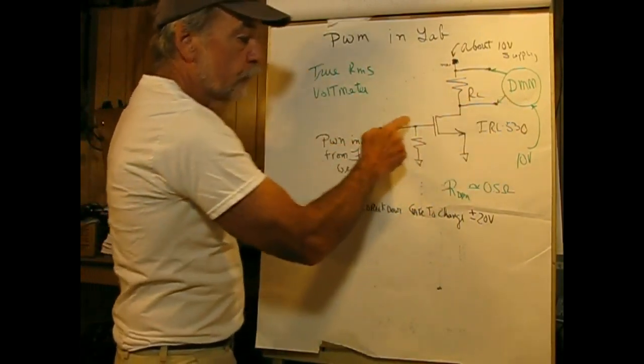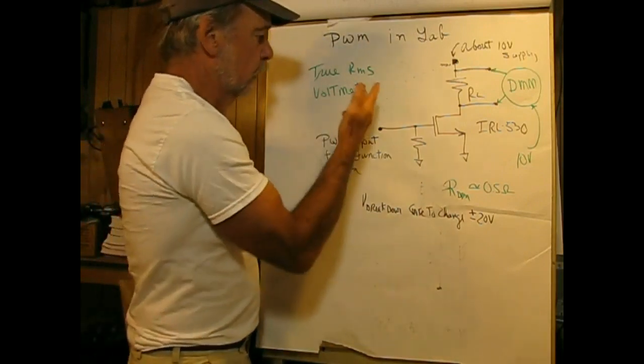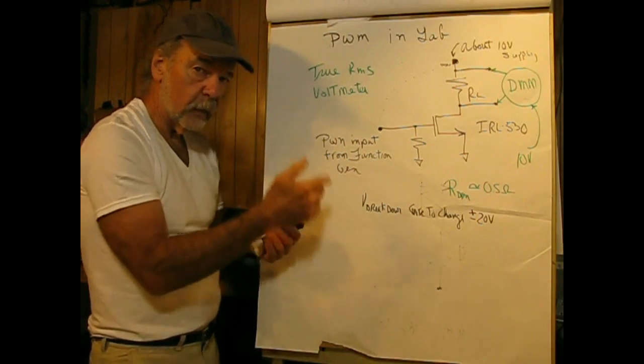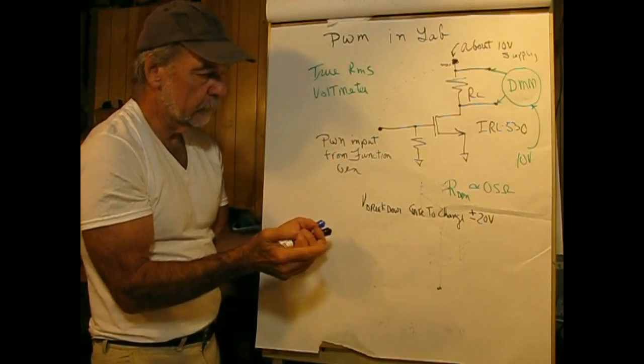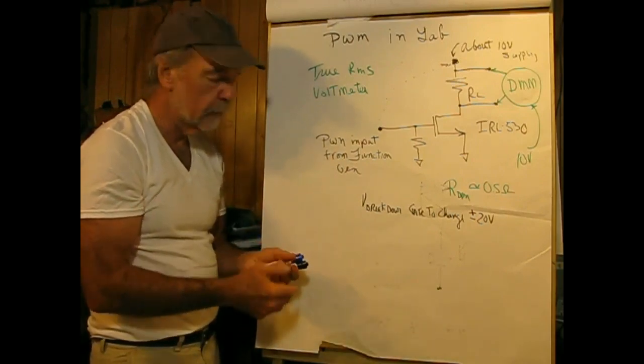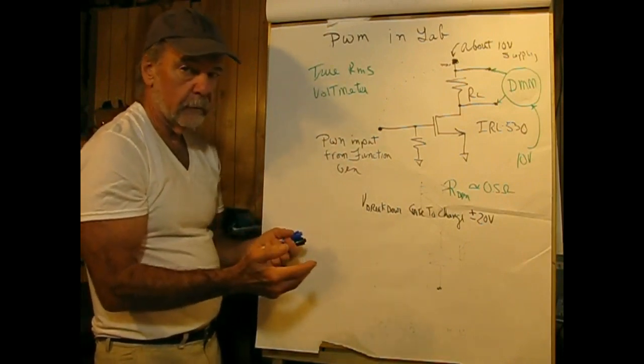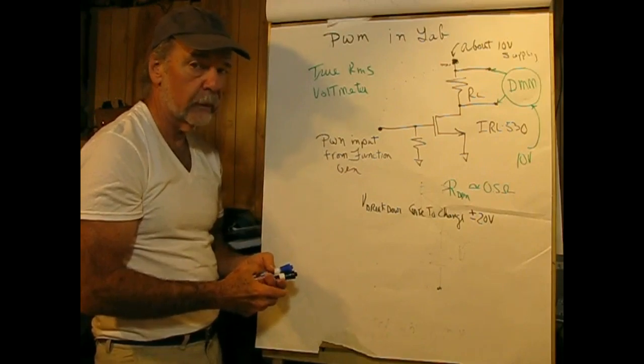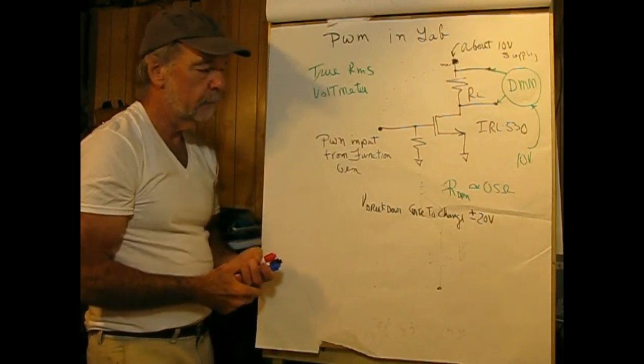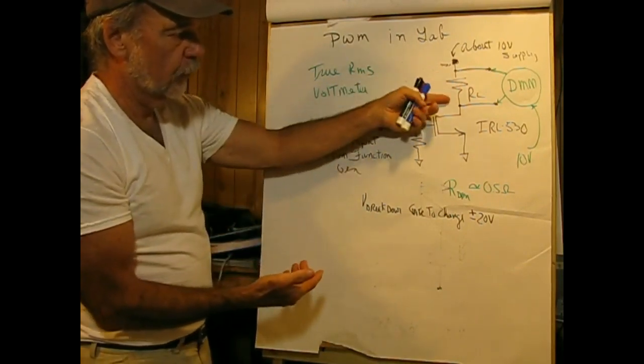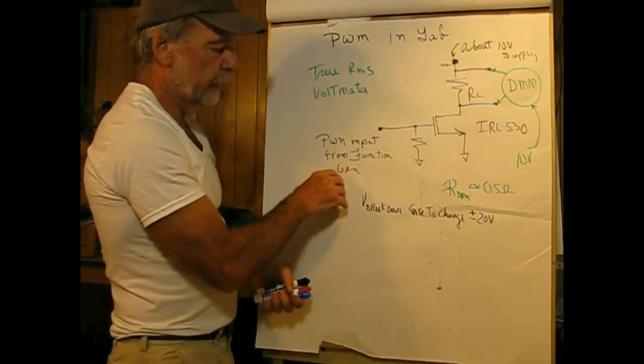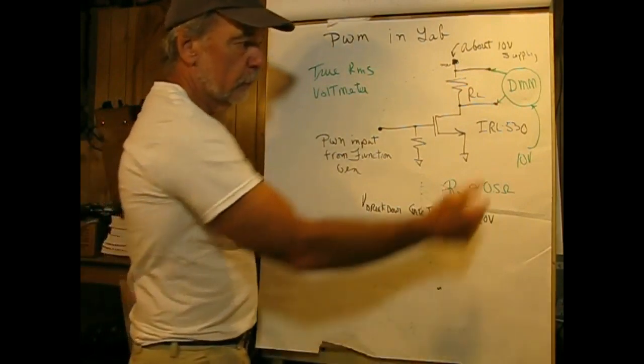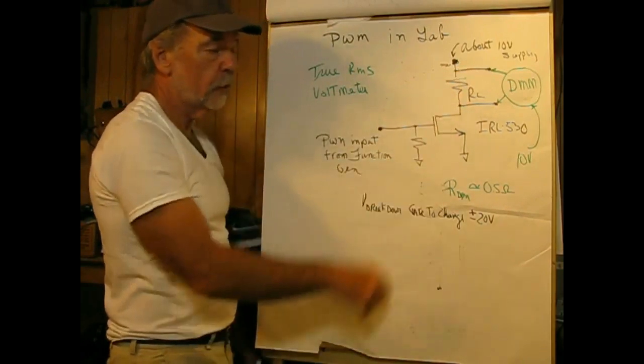This has to be a true RMS voltmeter, which is not something you buy at the local store for $6. A true RMS voltmeter will give you the RMS voltage of any waveform. What we buy at the store is a peak-reading meter for sinusoids only, calibrated in RMS — so any waveform other than a sinusoid is not going to read correctly. Once you get this setup with 10 volts drop across this resistor, all you have to do is change the input. On the DMM, to get the DC component you push the DC button; to get the AC component, you push the AC button. One meter does both functions without issue.